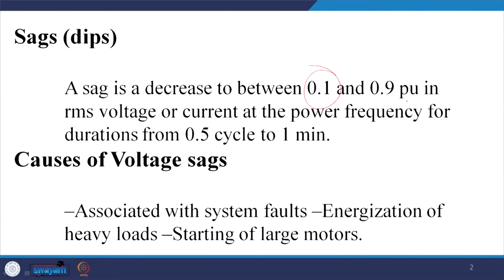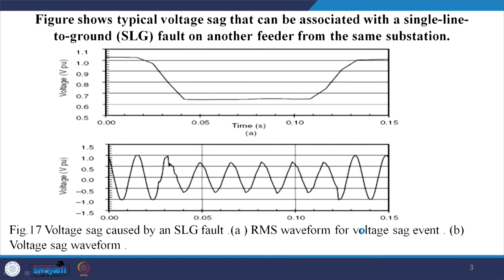Now we will talk about sag and dips. We have already defined sag; now we shall elaborate on different kinds of sags. Sag is a decrease of voltage between 0.1 to 0.9 per unit in RMS value at power frequency, during a period of at least 0.5 cycle and up to 1 minute. If it is longer than 1 minute, it can be considered an interruption. The causes of voltage sag are associated mainly with faults, energization of heavy loads, and starting of large motors, since the starting current of an induction motor is very high.